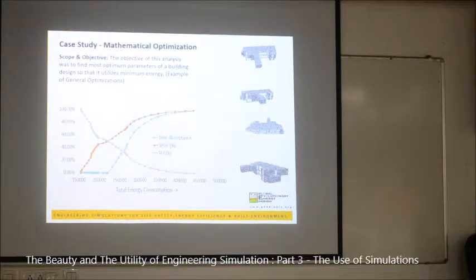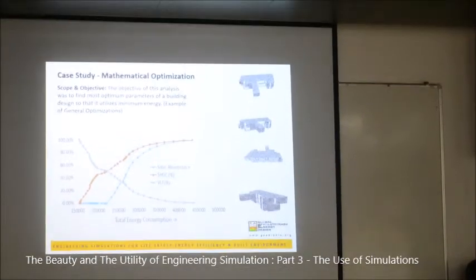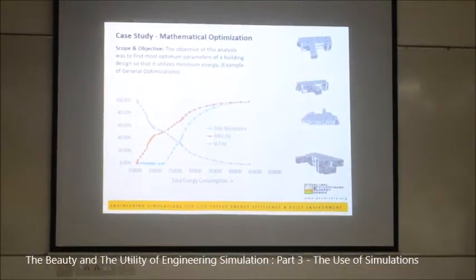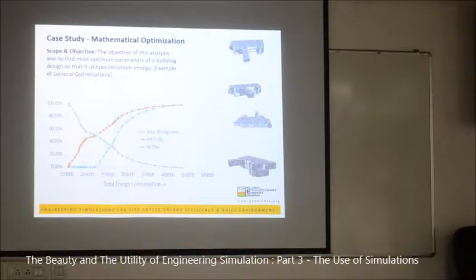Similarly, visual light transmittance. If outside is 8000 lux overcast sky, then how much light comes inside? 0.4 VLT means that 40% of that light is coming inside. But light diffuses. It comes here and it diffuses. See, that corner is least lit. This corner is highly lit. So the simulation software, specifically the building energy software, calculates all those kinds of things to very, very good accuracy.